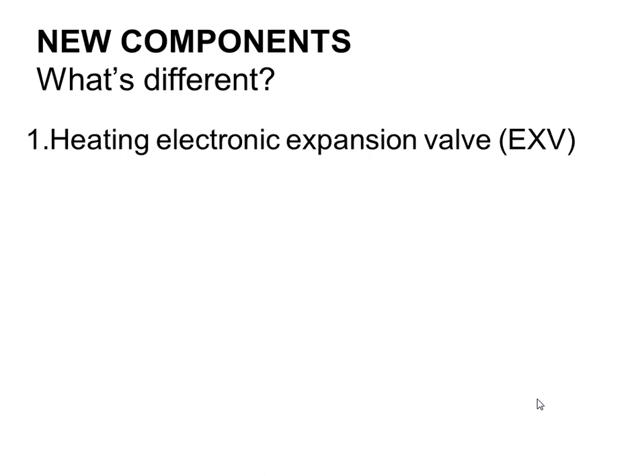Plus, he runs at a different speed. Some of the pieces inside this unit that are a little bit different than a regular heat pump or condensing unit, there's an electronic expansion valve, which is kind of like a TXV, a thermal expansion valve, but instead of doing it thermally, we do it electronically, which means that the control system actually modulates the position of the expansion valve to what it wants to see. We still have a TXV on these kind of projects. There's a TXV over at the indoor coil for cooling mode like it normally would be. The EXV is inside the heat pump factory installed for the heating mode, and it's a 600-step EXV that we position to the right capacity.